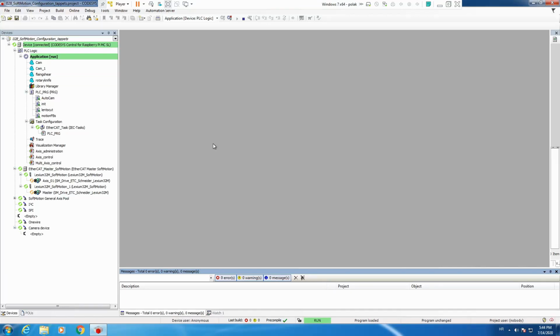Hello, today's topic is touch probe, or in fact print mark, or any sensor detection where we are using some kind of a sensor to capture a position. Now there are two ways to capture position. You can capture position inside a controller, or you can capture position inside the drive.